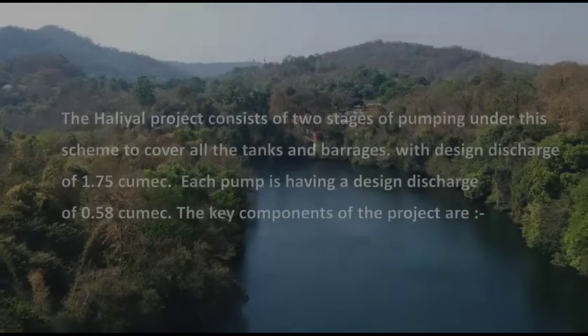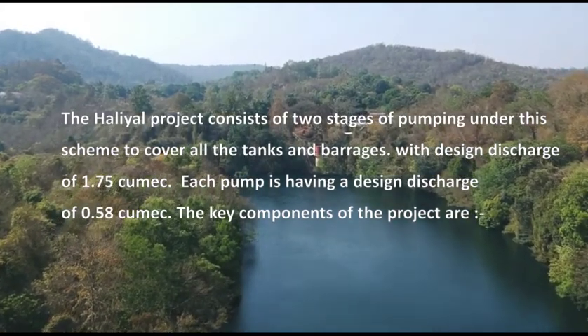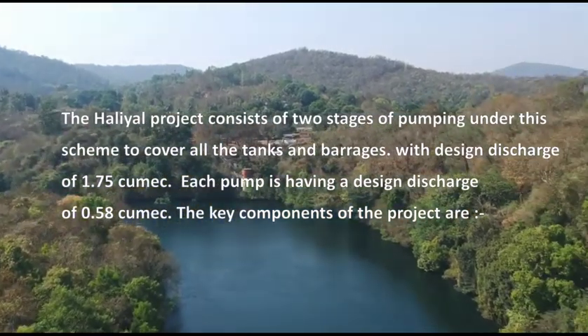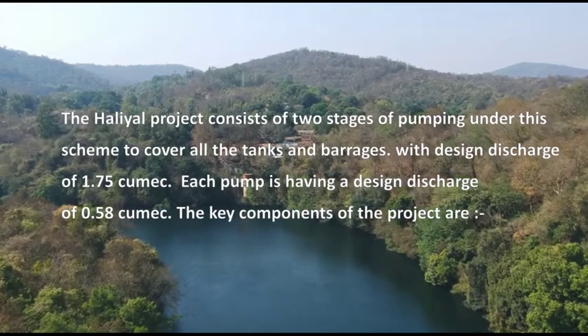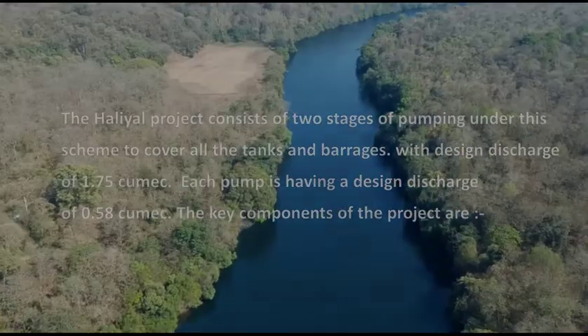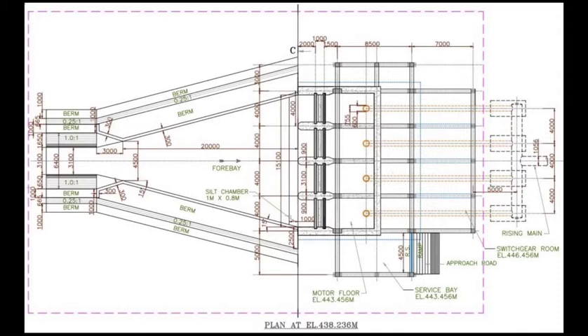The Haliyal project consists of two stages of pumping under this scheme to cover all the tanks and barrages, with a design discharge of 1.75 cubic meters per second. Each pump has a design discharge of 0.58 cubic meters per second. The key components of the project are the intake canal, 4 bays of 20 meter length, and the pump sump. A trash rack is provided for each bay. A silt trap is also provided to trap silt before entering the bay, and the rising main.